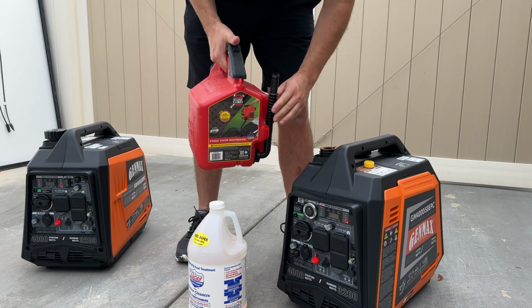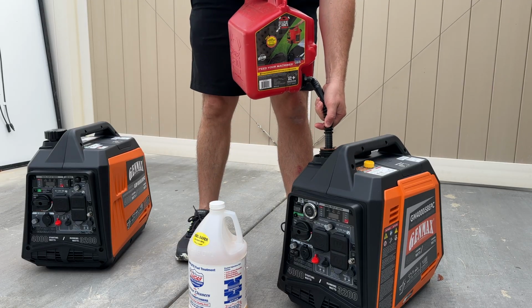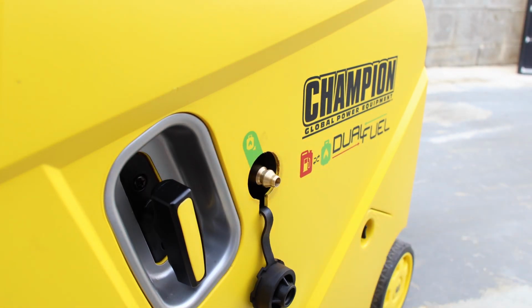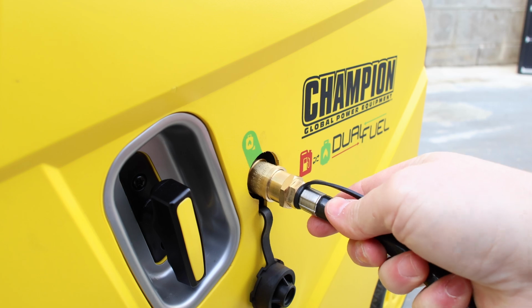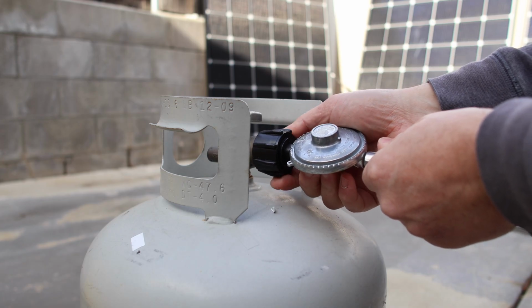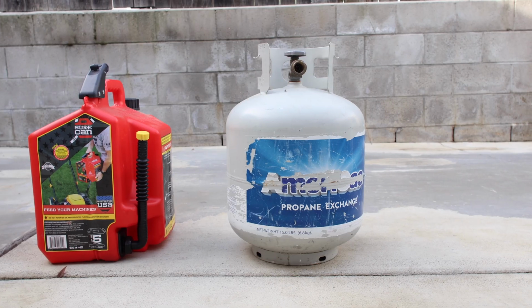normally be natural gas. Gas generators are typically easier as they don't need anything extra to run them as they have onboard fuel tanks. Tri-fuel and dual fuel generators will need an external fuel line and an external fuel source. Problems that you can find with this are either valves going bad or regulators going out at inopportune times.